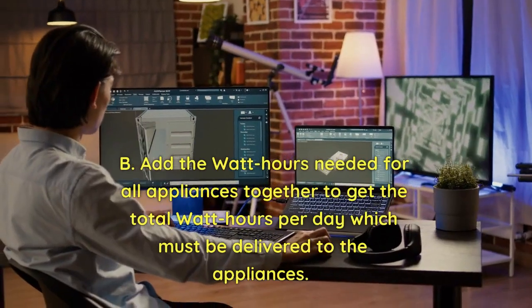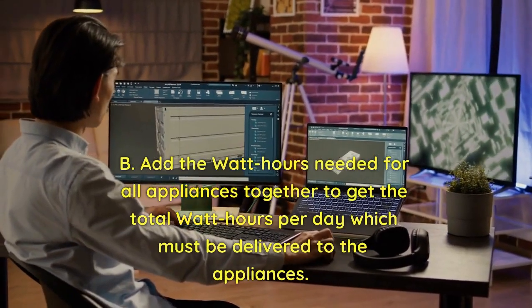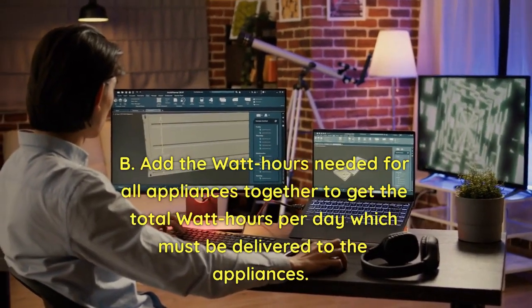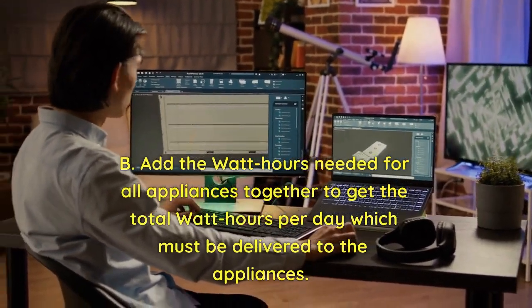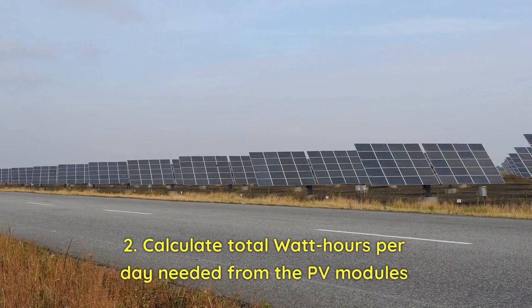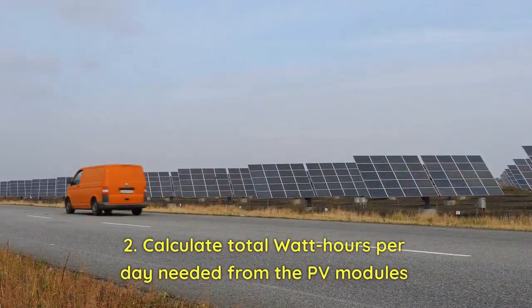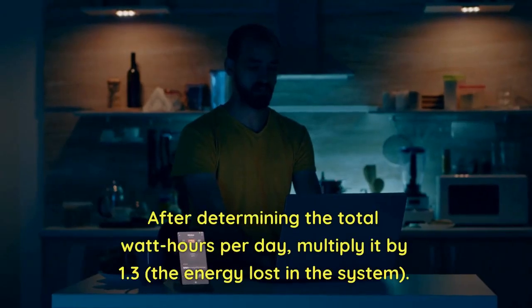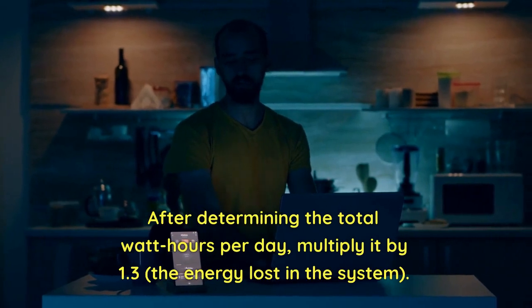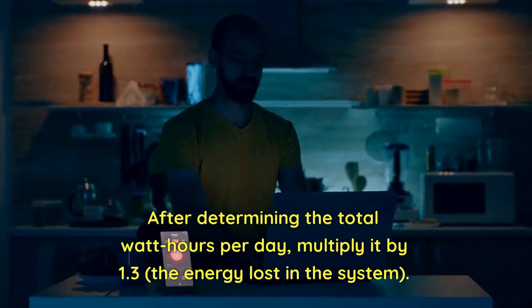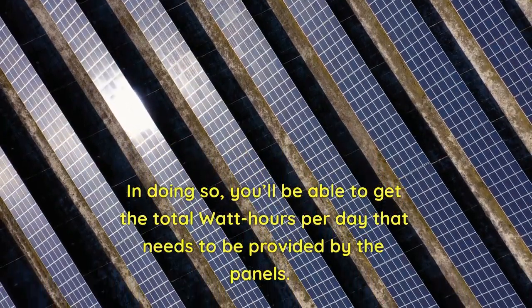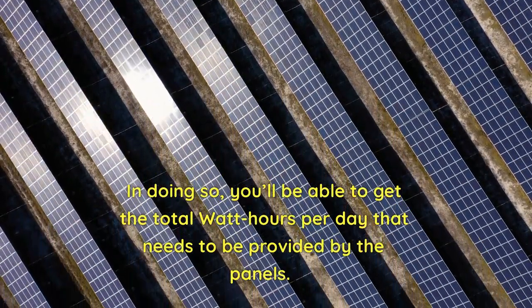B. Add the watt-hours needed for all appliances together to get the total watt-hours per day which must be delivered to the appliances. 2. Calculate total watt-hours per day needed from the PV modules. After determining the total watt-hours per day, multiply it by 1.3, the energy lost in the system. In doing so, you'll be able to get the total watt-hours per day that needs to be provided by the panels.